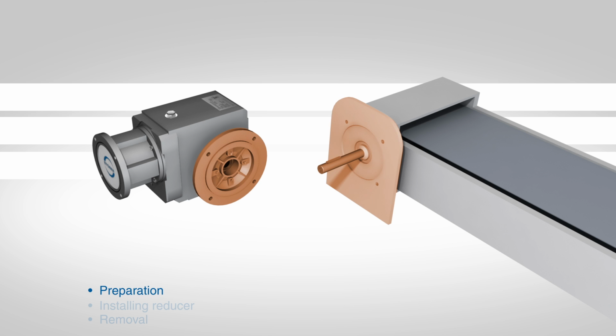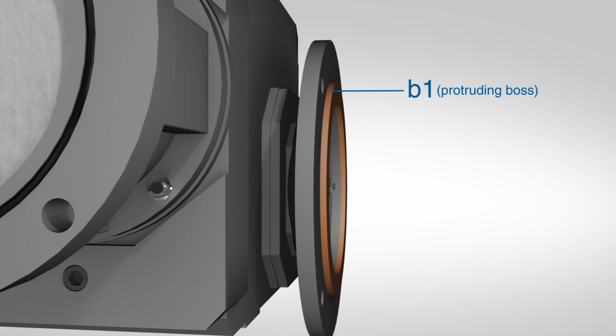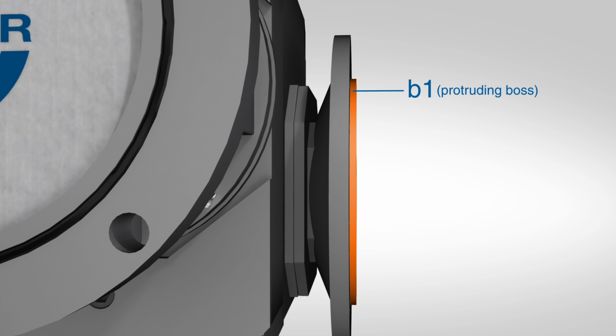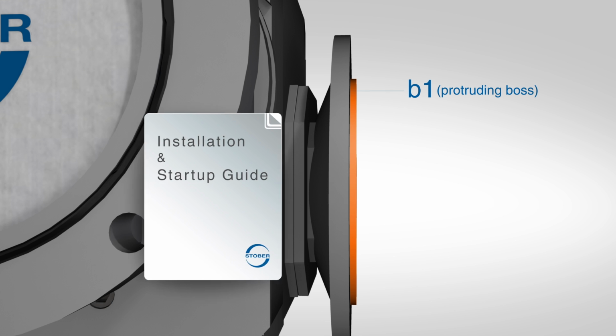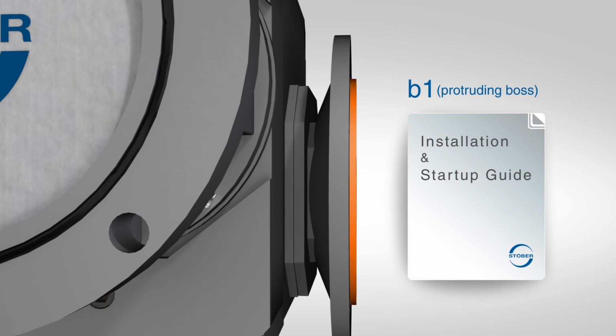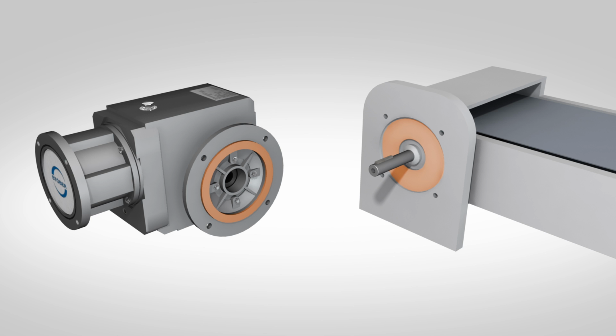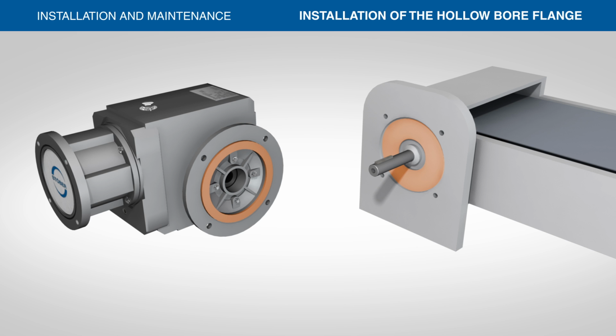Check the flange and machine mounting interface to ensure they have compatible dimensions for proper installation. The first dimension to check is the protruding boss, or dimension B1, of the flange. This portion of the flange will be utilized for centering the gearbox on the conveyor to ensure concentricity. The tolerance of the protruding boss, dimension B1, is shown in Table 2. The machined bore in the machine mounting surface should fit this boss accordingly.